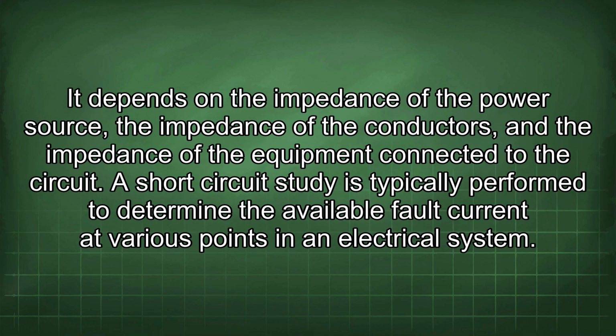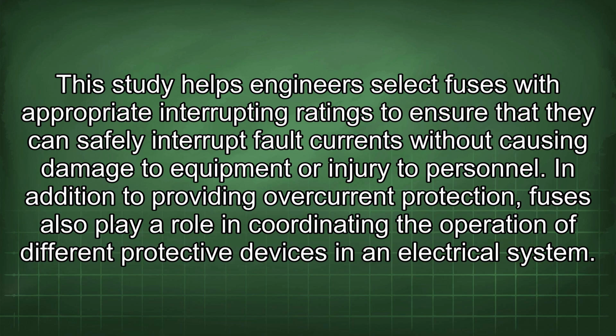It depends on the impedance of the power source, the impedance of the conductors, and the impedance of the equipment connected to the circuit. A short circuit study is typically performed to determine the available fault current at various points in an electrical system. This study helps engineers select fuses with appropriate interrupting ratings to ensure that they can safely interrupt fault currents without causing damage to equipment or injury to personnel.